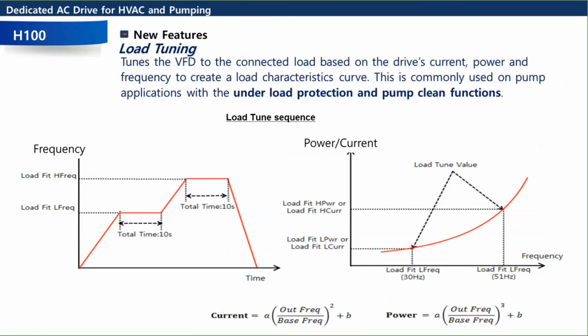All right, so here's another one. This is a really nice feature for pumps, which is called load tuning. We briefly mentioned auto tuning. Auto tuning is tuning the drive to match up with the motor. So you put all your motor parameters in there. How many poles is the motor? What's the rated slip or the RPM of the motor? What's the kilowatt capacity? Actually, it'll be horsepower on the H100, which is nice for us Americans. So you plug in all that stuff and you do an auto tune. That gives you a little bit more efficient operation. Squeezes the most volts per amps out of the drive. Load tuning is tuning the output V by F to the load.